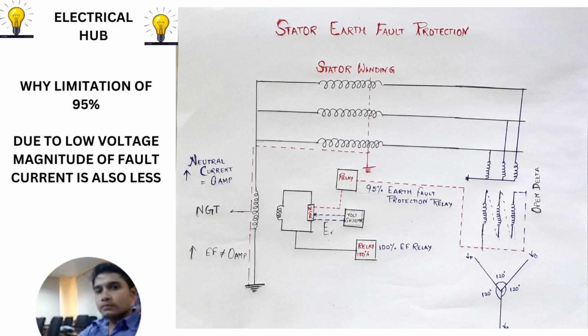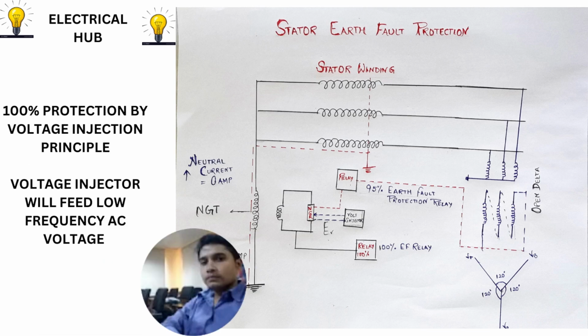Now the question comes, why can we not reduce the setting so that if there is a voltage drop, the relay should trip? It is because, due to unbalanced load, there can be a small amount of current flowing through the neutral grounding transformer. If this part is also taken, then it will always trip. That is why through this relay we protect only 95% of the winding. But all of us know that 100% of the stator winding is protected.